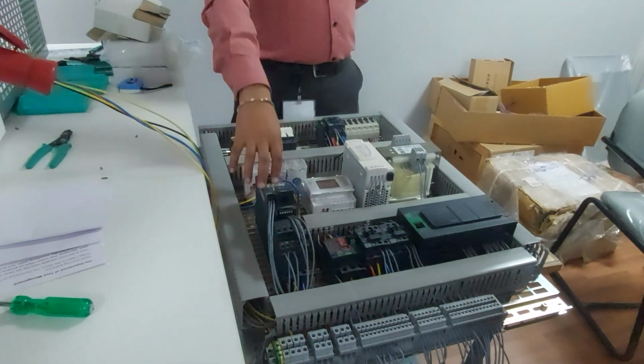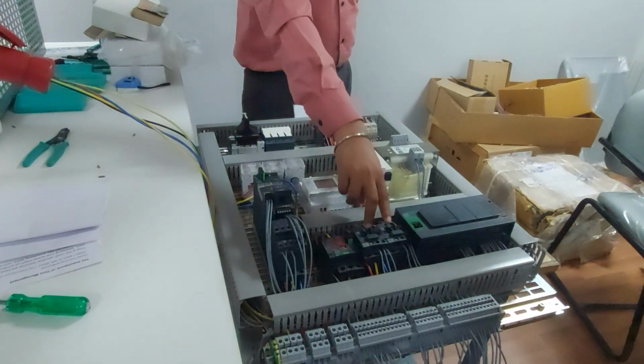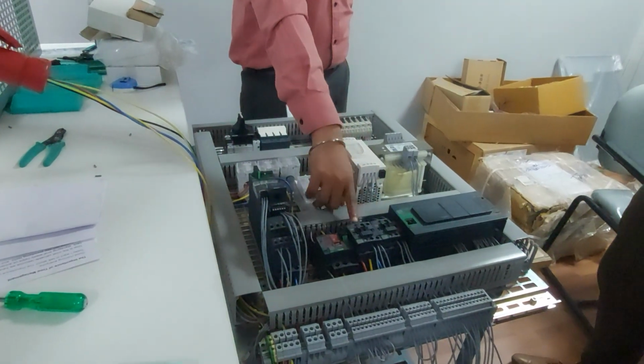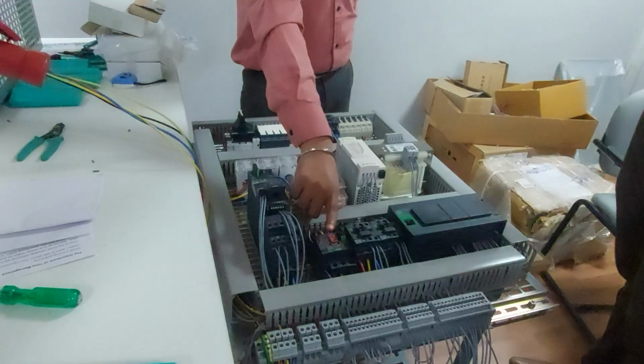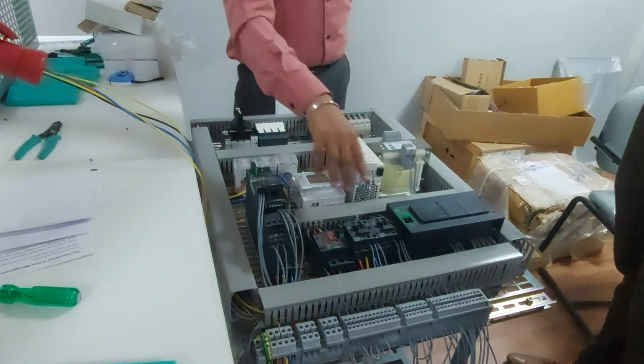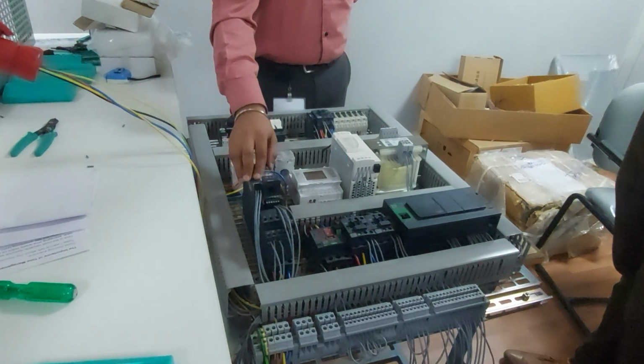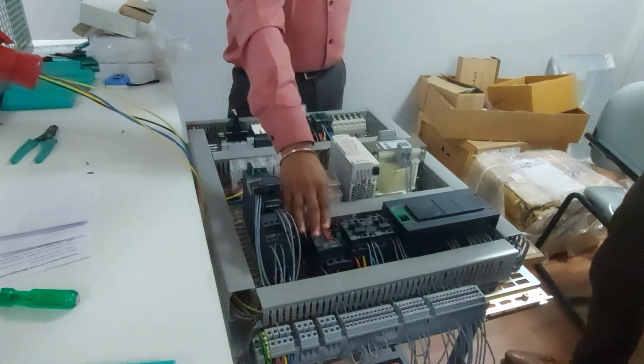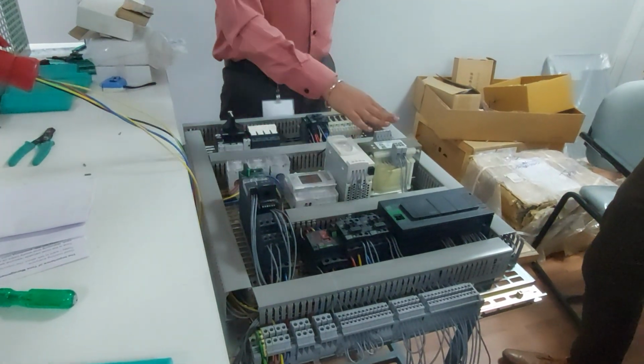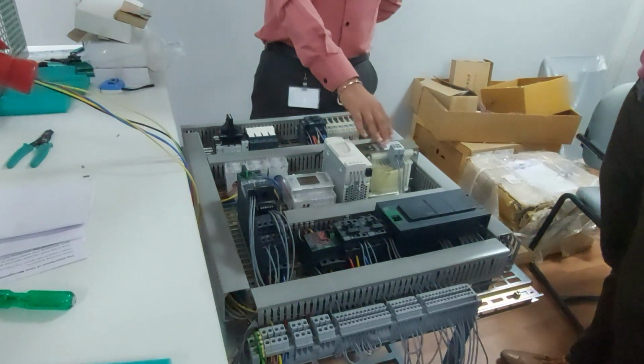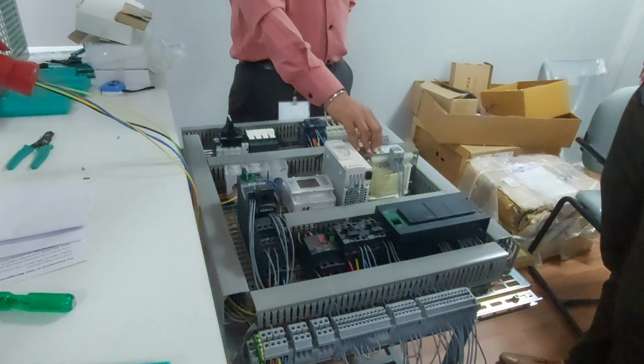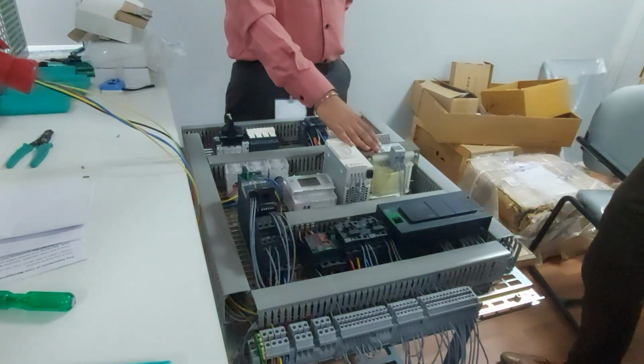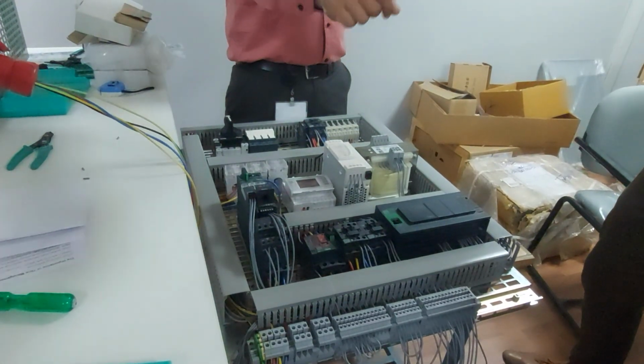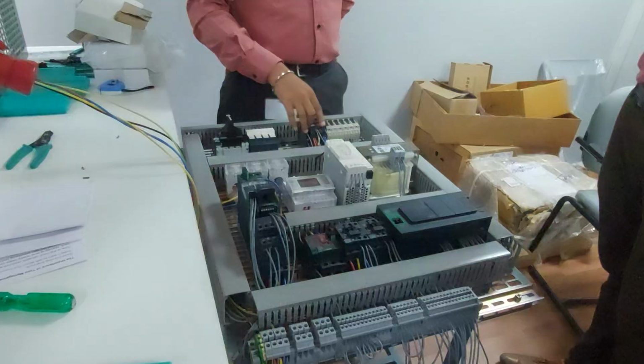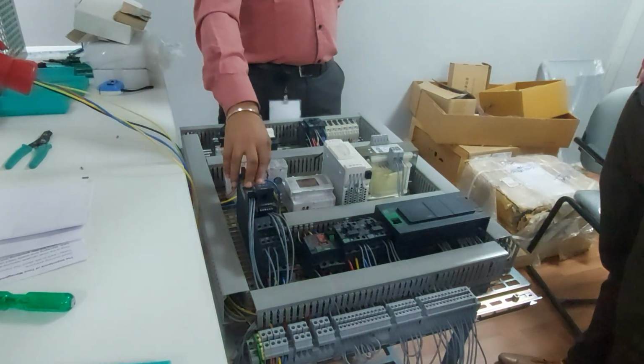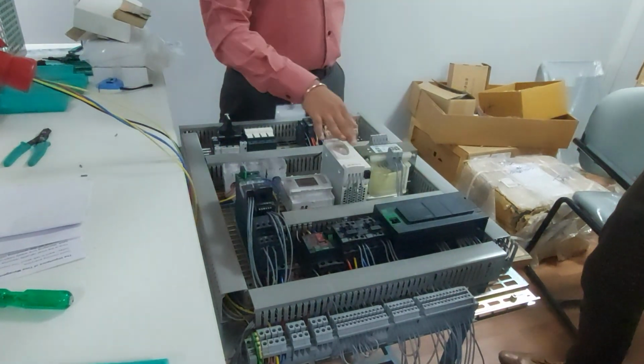And why we are using TCS drive here is that for forward reverse we would use two contactors, and for motor protection we would use one MPCB. But in this case, all three are combined in one. So forward reverse and MPCB motor protection are in one. The transformer we have used for the control circuit, 24 volt AC. SMPS is for limit switches, we have 5 limit switches. And for the TCS drive we have 24 volt DC, and also for the PLC.